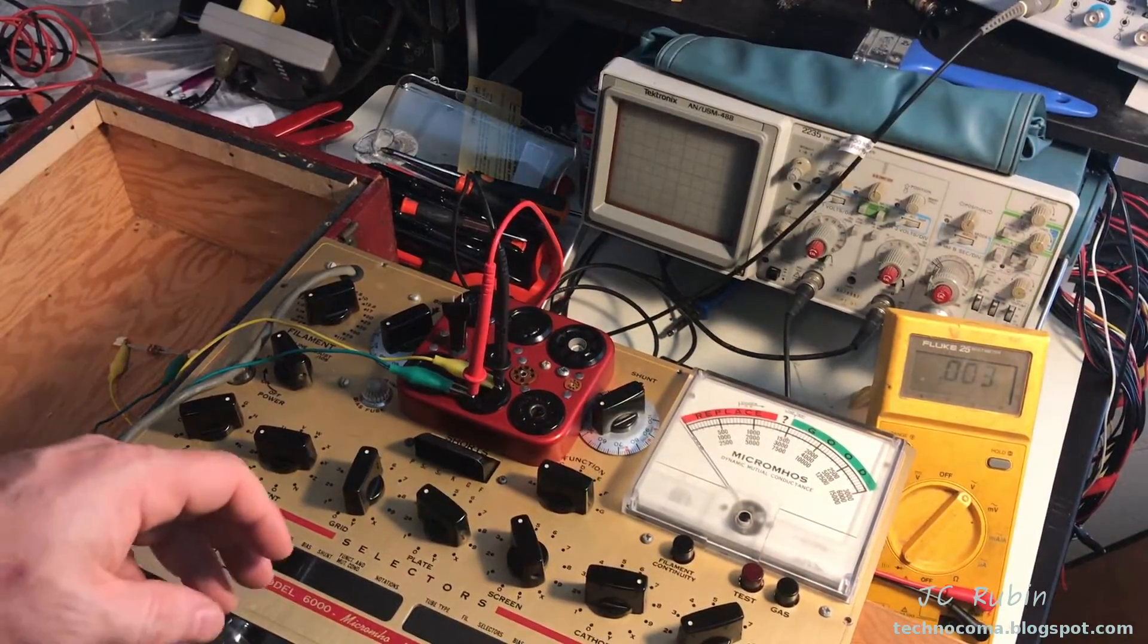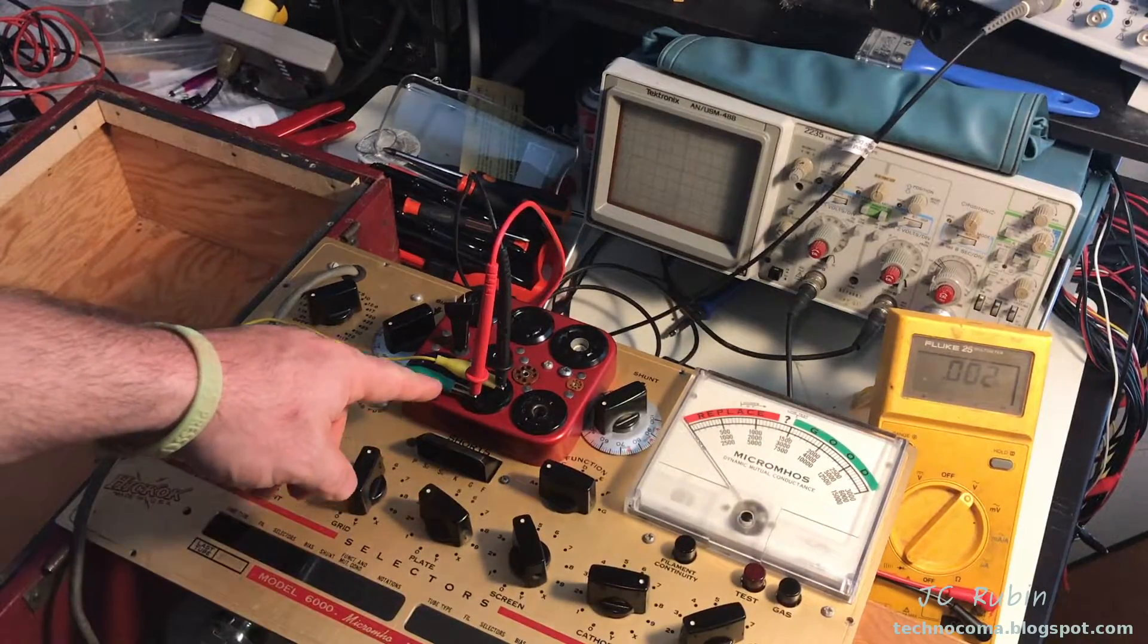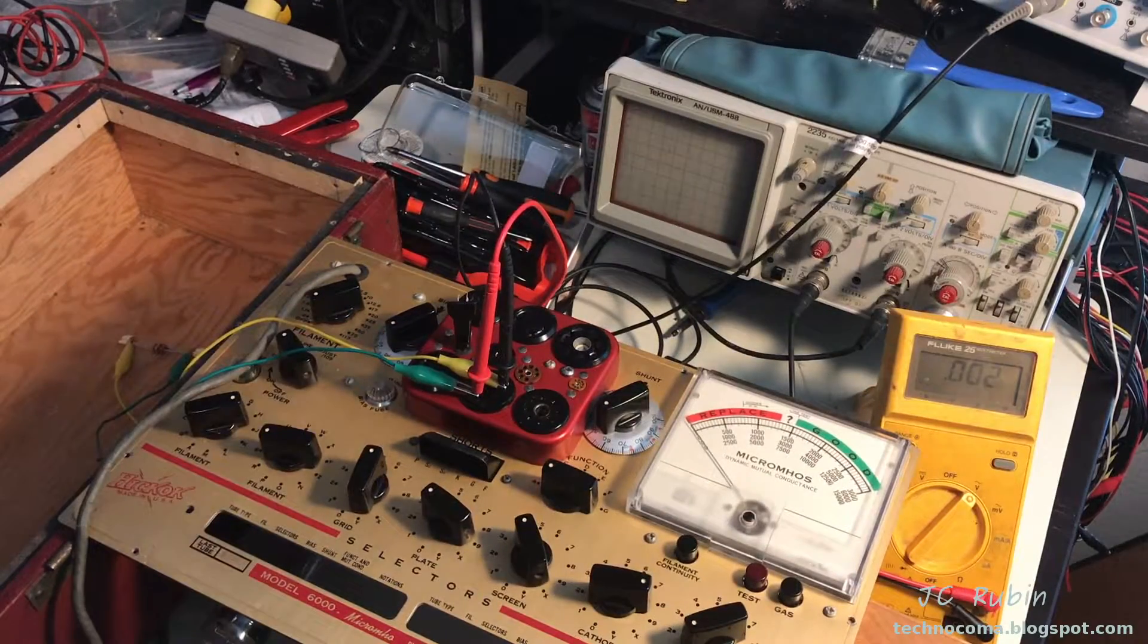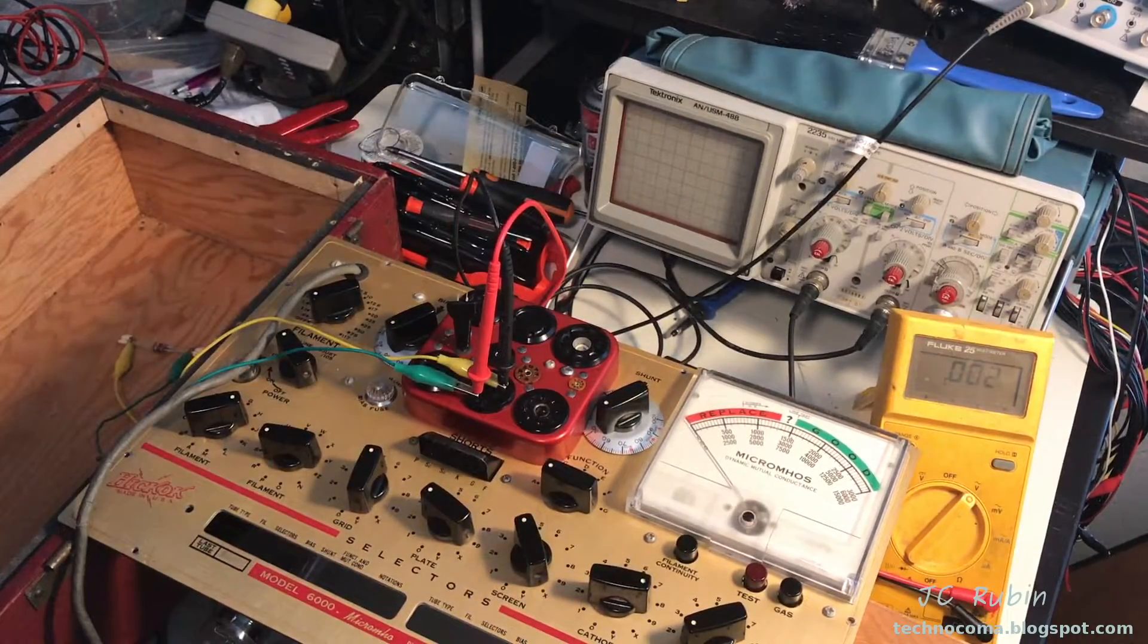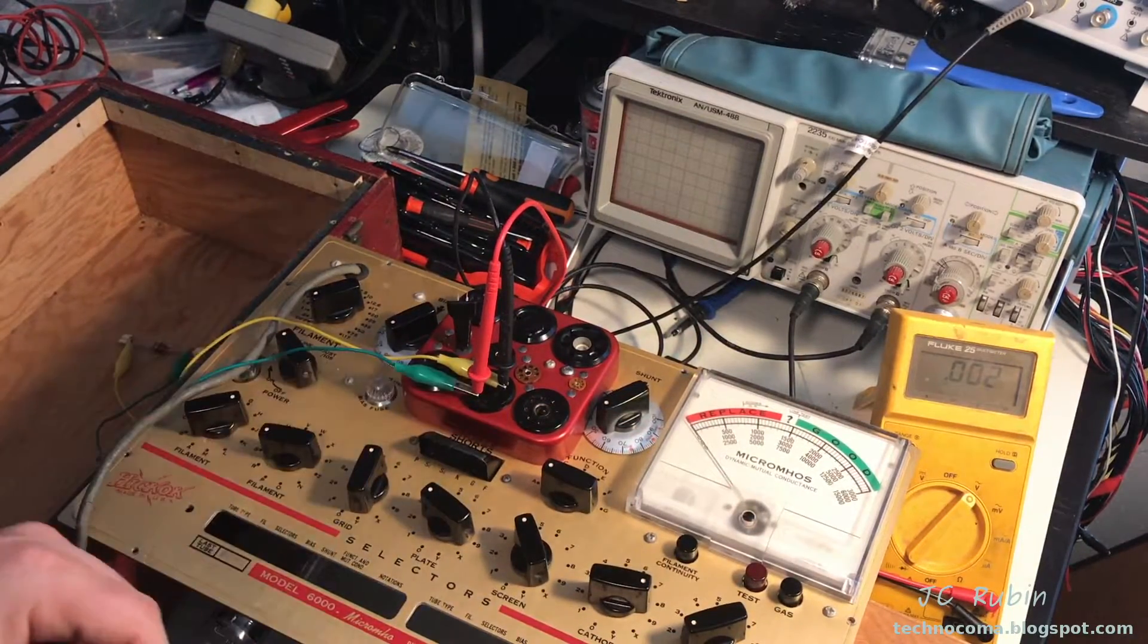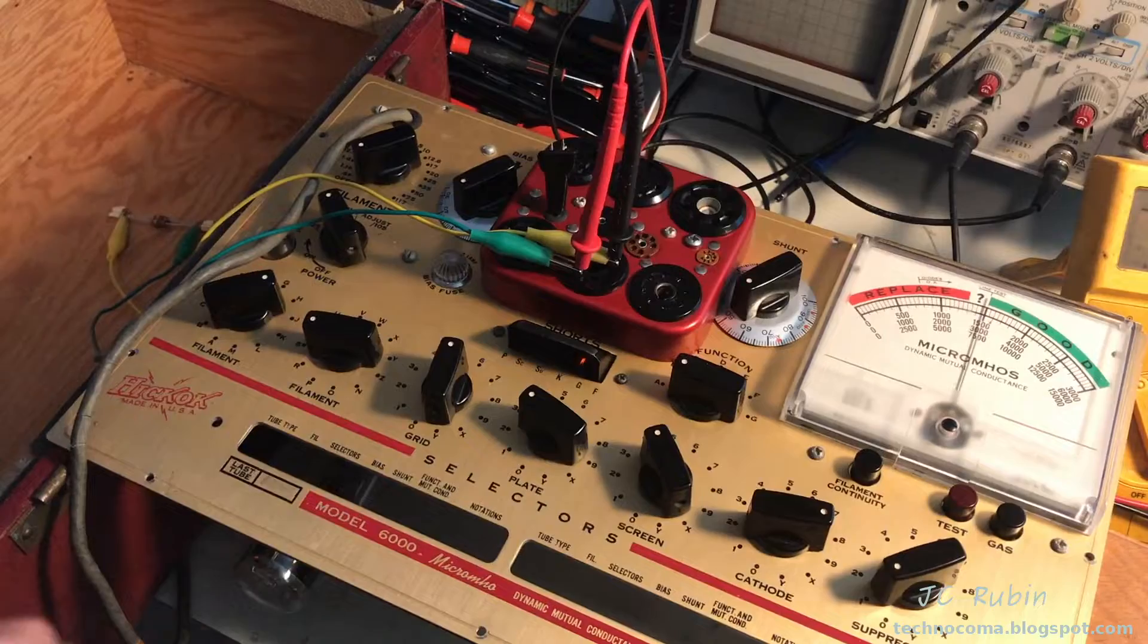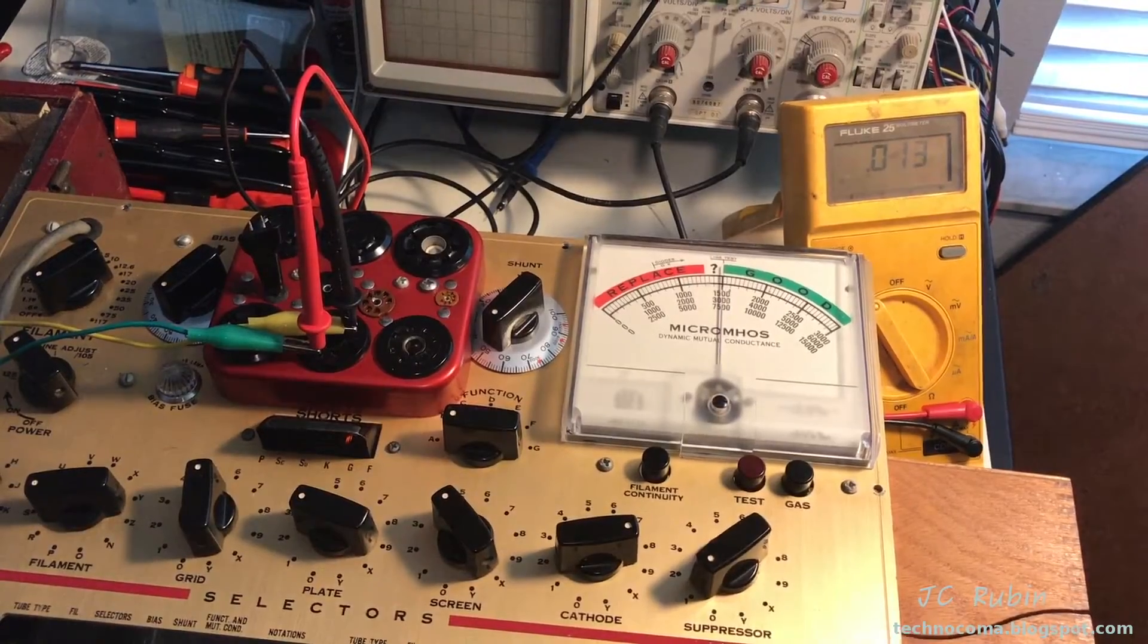Before we turn anything on, I just want to talk about the layout. We can see the probes are going directly into three and eight for our next test. We could also see that we have these alligator clips making their way down to the shunt in the box. This brings us to our next test, a test of the plate voltage on pins three and eight. We should expect that when we hit the test button we should see a value of 150 volts plus or minus three volts.